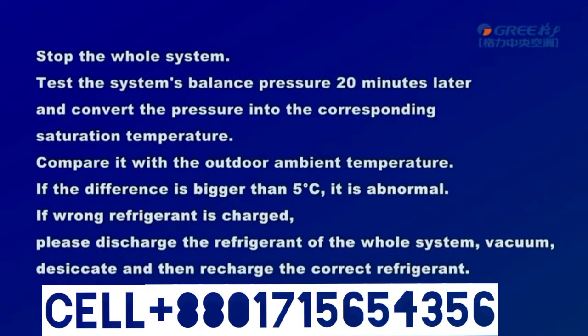3. Wrong refrigerant. If it is not charged with R410A, the system may not be operated normally. Confirmation of refrigerant. Stop the whole system. Test the system's balance pressure 20 minutes later and convert the pressure into the corresponding saturation temperature. Compare it with the outdoor ambient temperature. If the difference is bigger than 5 Celsius degree, it is abnormal. If wrong refrigerant is charged, please discharge the refrigerant of the whole system, vacuum, desiccate, and then recharge the correct refrigerant.